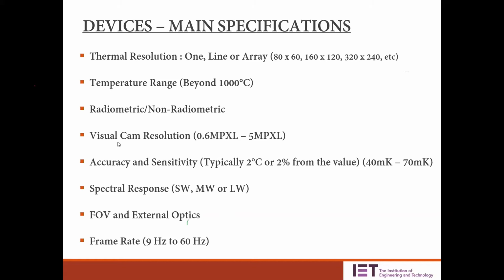And these days they have a visual camera inbuilt, because they have these interpolation techniques where they will put your visual photograph and the thermal image together, and integrate the two images and create one. And it's better to identify certain components in, let's say, a very dark, very low light condition. Using the inbuilt torch or the lighting phenomena, we can identify those components easily with the thermal resolution and the pattern on it.